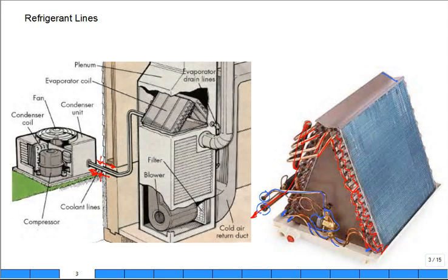This right here is the expansion valve. They're very close together. Because if there is any, this fluid in here is going to be cool, but if there's any stray heat transfer, well it's tucked into the duct. It's into the duct. So it's not like you have the expansion valve very far away from the coil and then there might be stray heat transfer into it before you get to the coil.